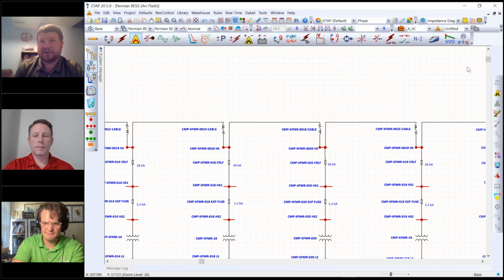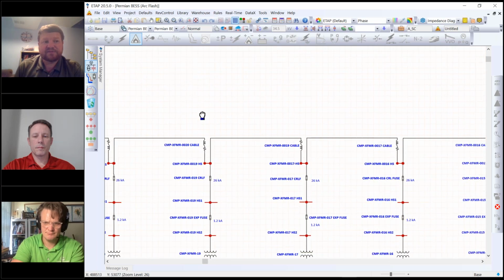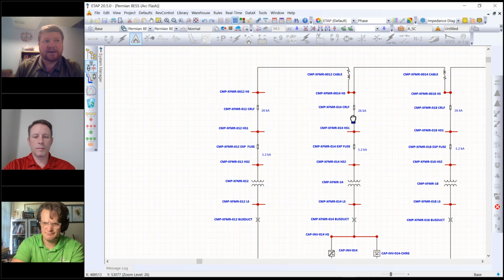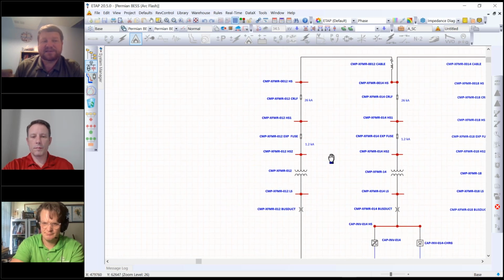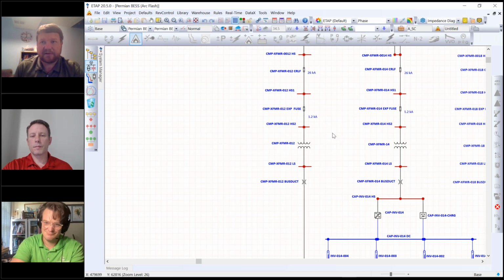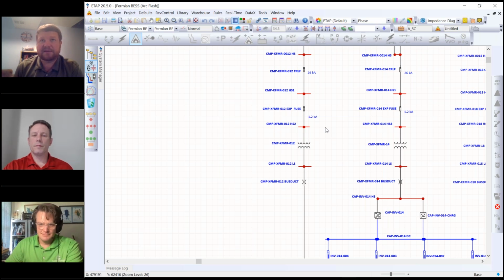A lot of fuses will clear. What ends up happening when you're looking at a transformer low side fault is that fault current is reflected through the high side through the turns ratio of the transformer. So when you have a high medium voltage and a low voltage, there's a lot of transformer turns there, and that current can be divided by 30 or 60 times. So that CLF fuse may operate very quickly for a medium voltage fault, but when it sees a low voltage fault reflected through that transformer, that current is significantly lower. And because of that low fault current, it takes a long time for those fuses to burn or even pick up. Sometimes it's below the pickup value of the fuses themselves, which can create these very long clearing times.